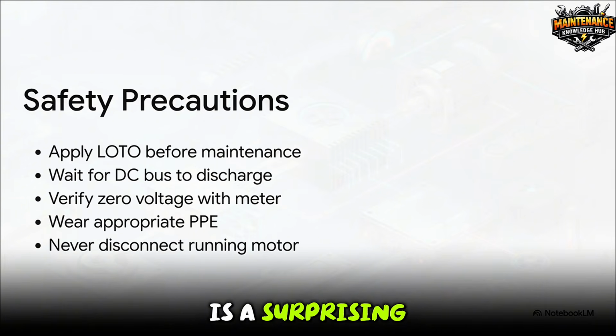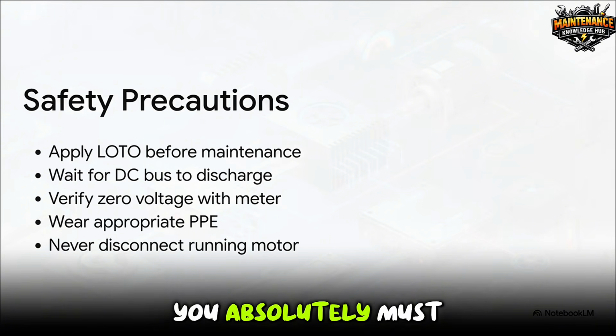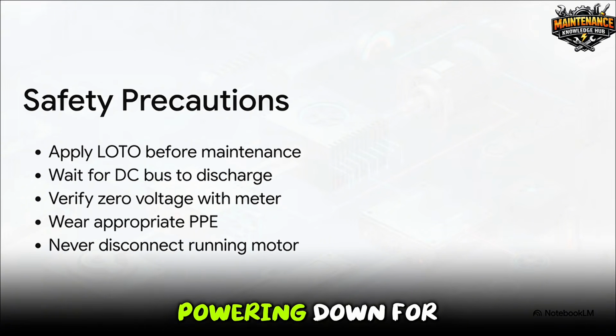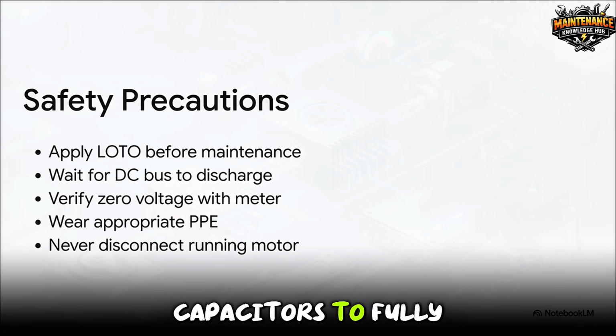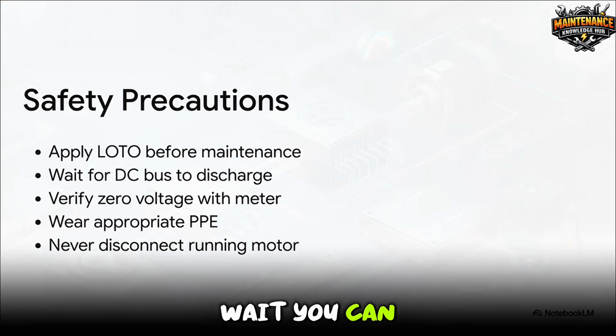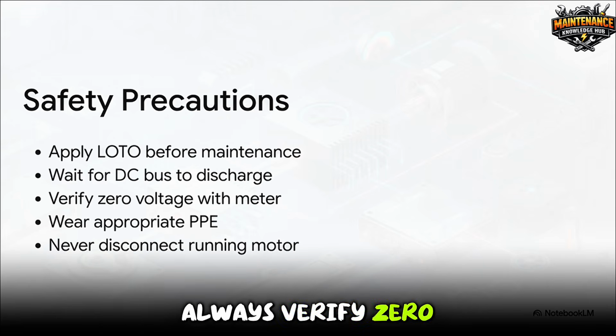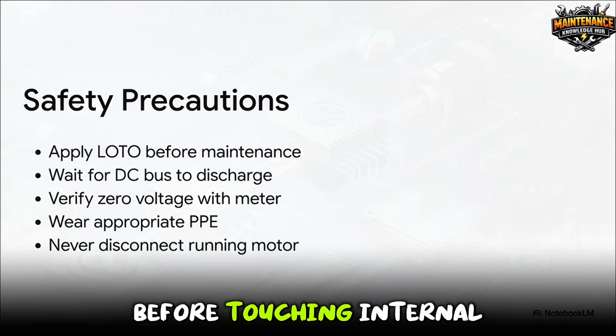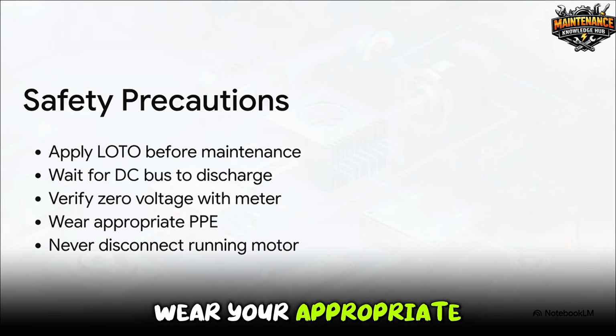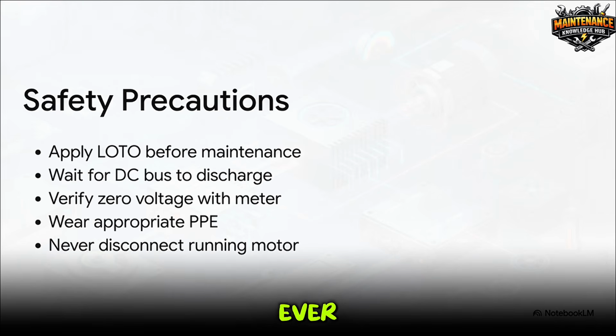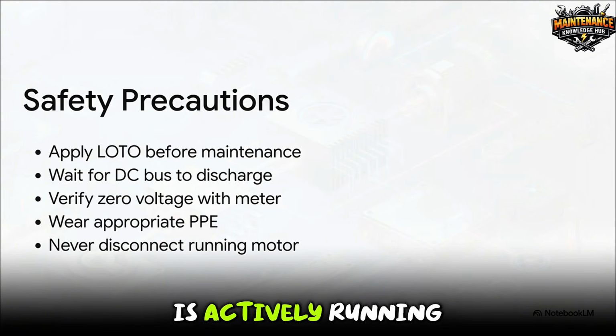Next, and this is a surprising and vital danger, you absolutely must wait several minutes after powering down for the DC bus capacitors to fully discharge. If you don't wait, you can literally receive a lethal shock even with the main power switched off. It's no joke. Always verify zero voltage with a properly rated meter before touching internal components. Wear your appropriate PPE, and never, ever disconnect the motor while the VFD is actively running.